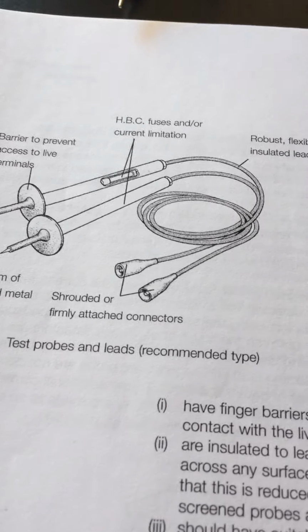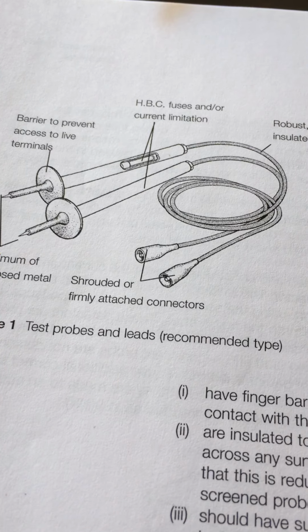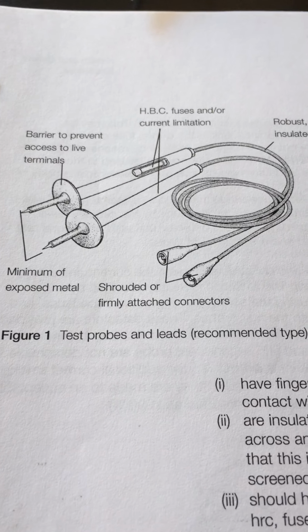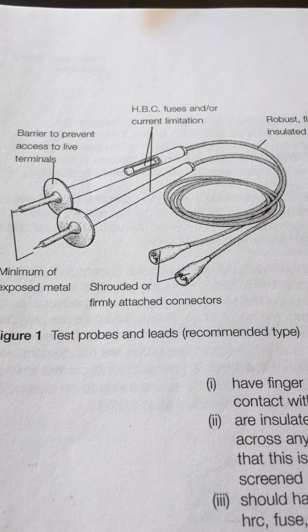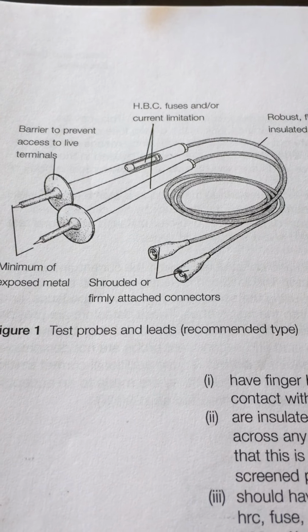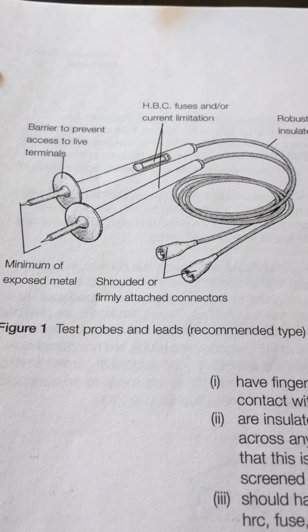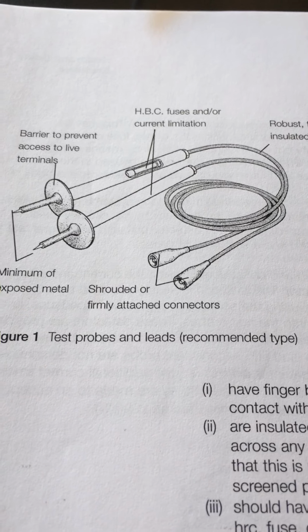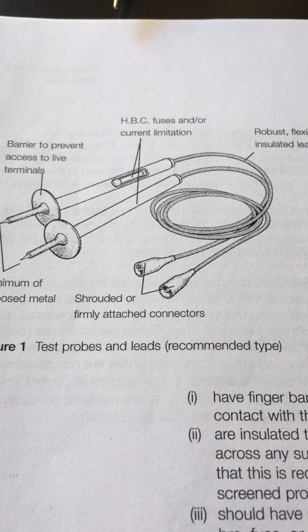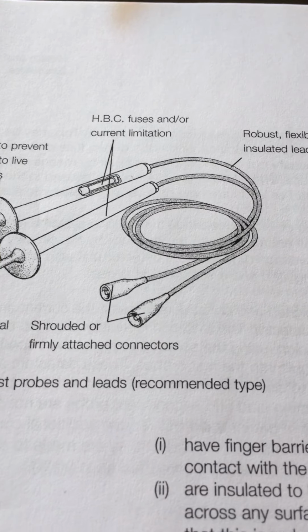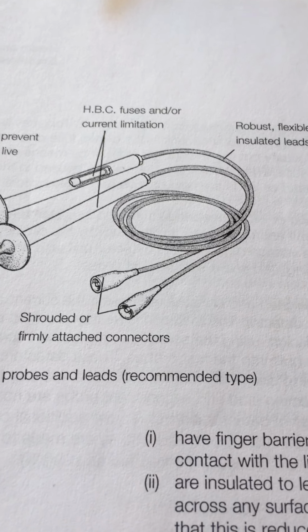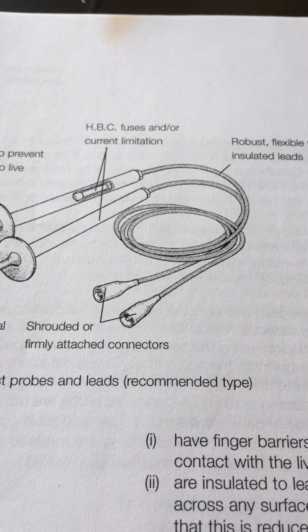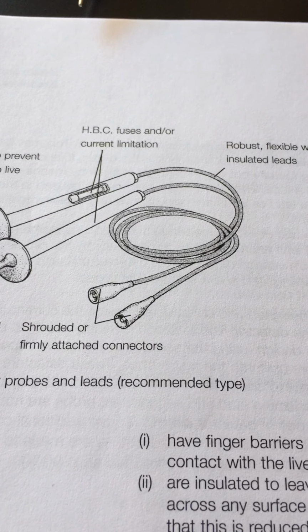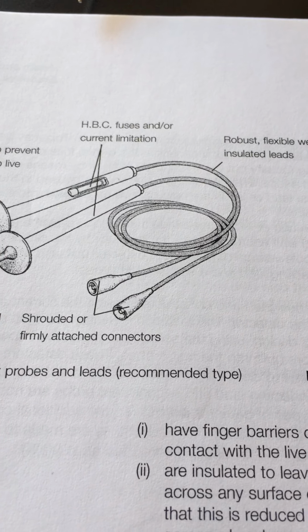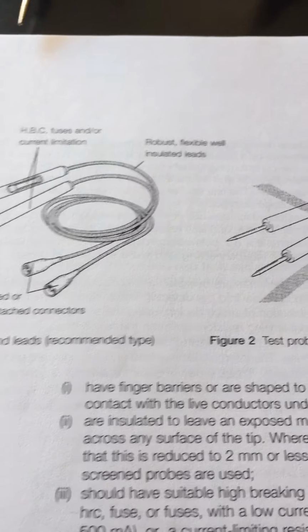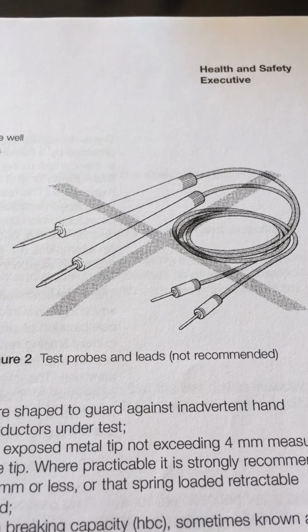Now the basics of it is, well, we can see there, that's an acceptable set of probes and leads. If we talk about the tip of the probe, it says in the document 4mm, preferably 2, we can see that being demonstrated there. Finger guards to prevent your fingers falling onto the live terminals. Fused or current limiting. Sometimes you'll have fuses in the leads themselves or at the end of the probe there, as you can see. Sometimes it'll be in the units that the leads are plugging into that they're protected by. And there's an example of a non-compliant set.